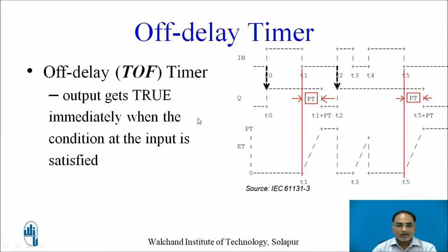The output gets true immediately when the input condition at the timer is satisfied. At t0, when input changes from 0 to 1, output also changes from 0 to 1 at the same time, but the timer is still in the off state. At t1, when input changes from 1 to 0, the timer starts and the ET value starts incrementing towards the PT value.